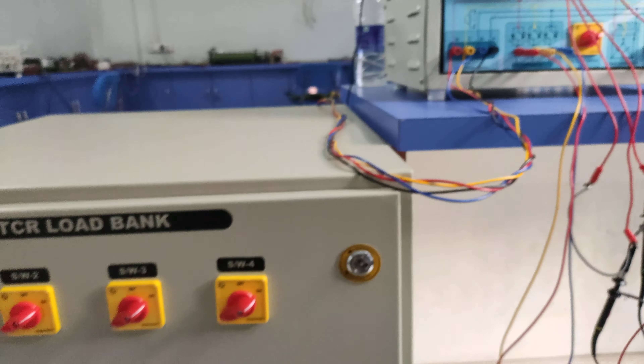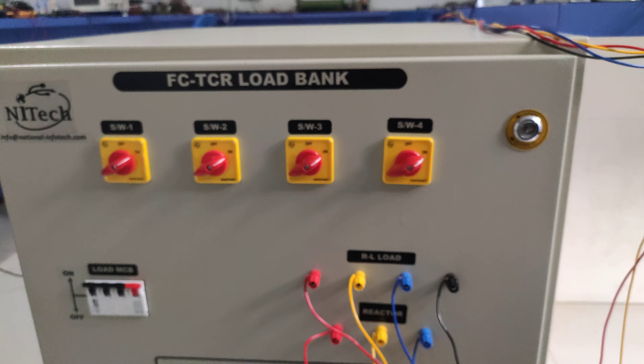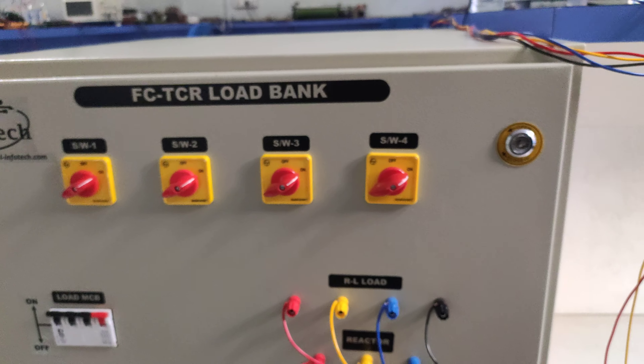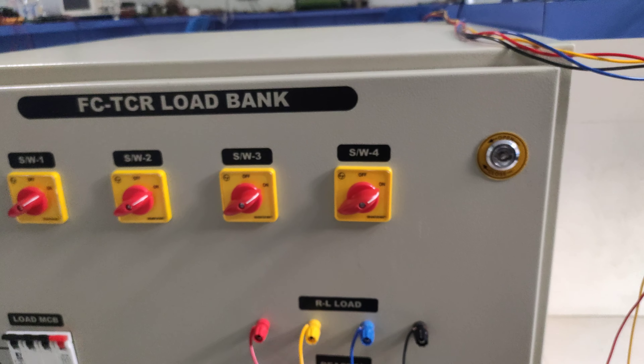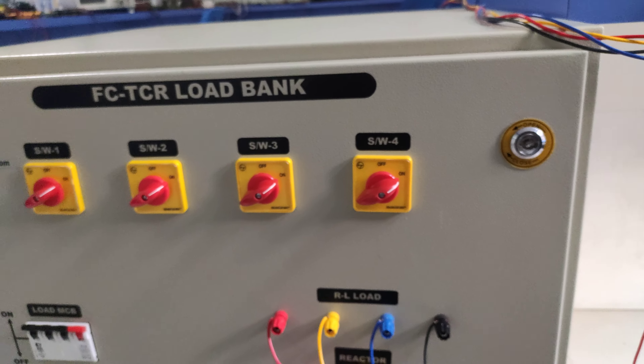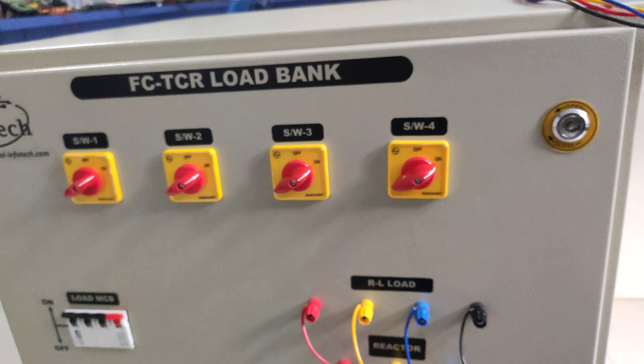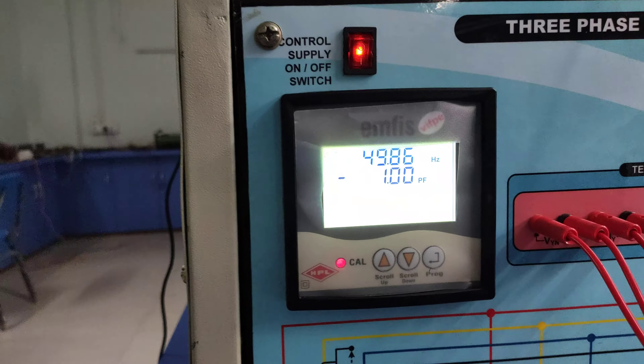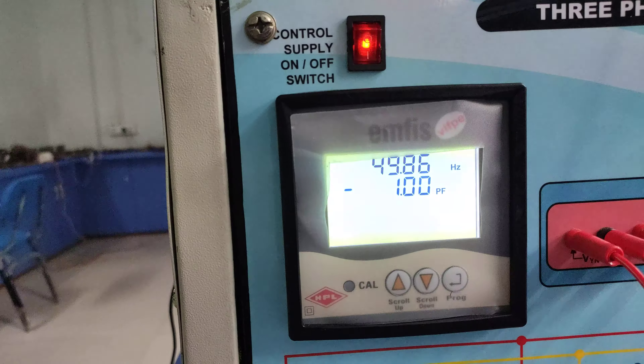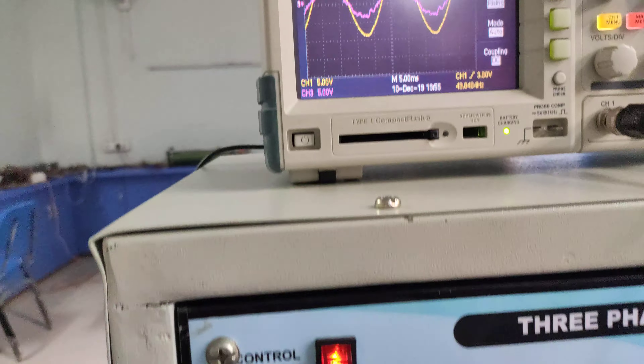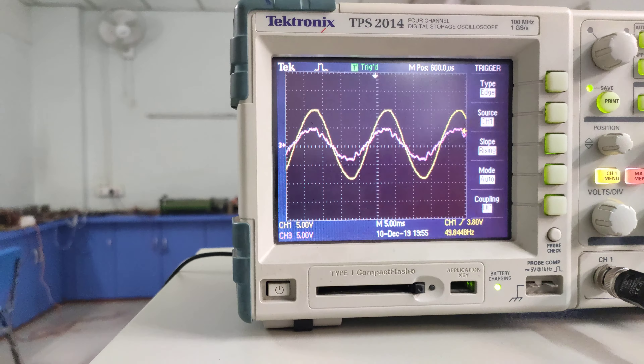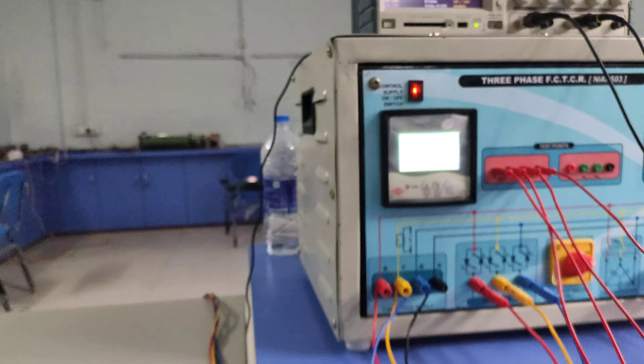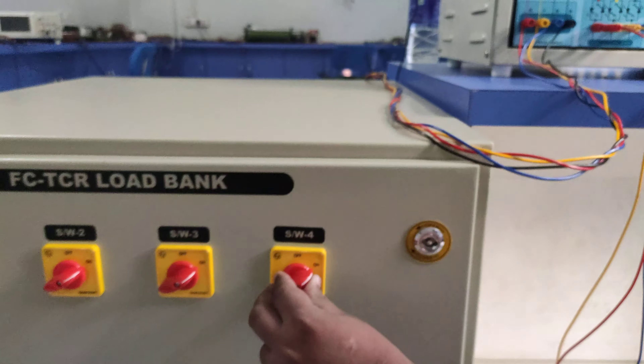In closed loop mode, by changing your load, the controller takes automatic action to control the firing angle of the thyristor bank as well as the switching of the reactor. We observe our power factor as well as current and voltage waveforms to bring the power factor to unity.